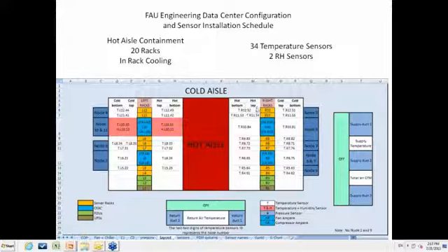And in the middle is a hot aisle. The two columns of numbers on either side of the racks indicate the sensors that are attached to that part of the rack. So the ones labeled hot are on the hot side of the rack, and the ones labeled cold are on the inlet side, of course. These temperature sensors, the two at the upper left-hand corner, which I'm pointing to, are connected to node 4.